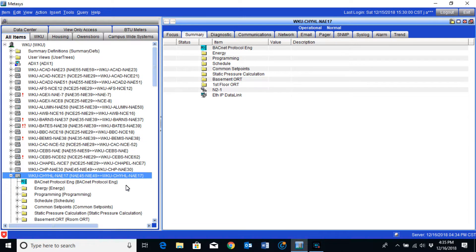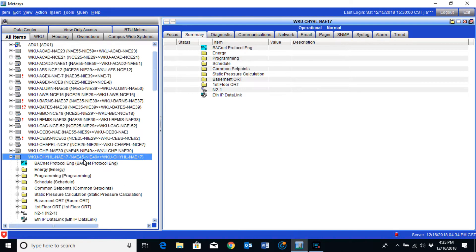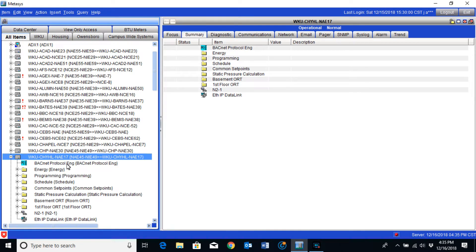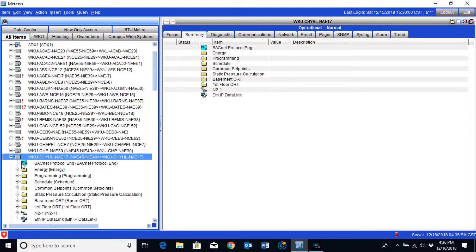So the server is a way of being able to see an entire site at one time. The server is on the local area network, and each of these devices are as well. The NAEs, the NIEs — all of these devices are connected directly to the local area network. For those of you who may not be familiar with the difference between an NAE and an NCE: NAE stands for Network Automation Engine. That's basically what those devices are.